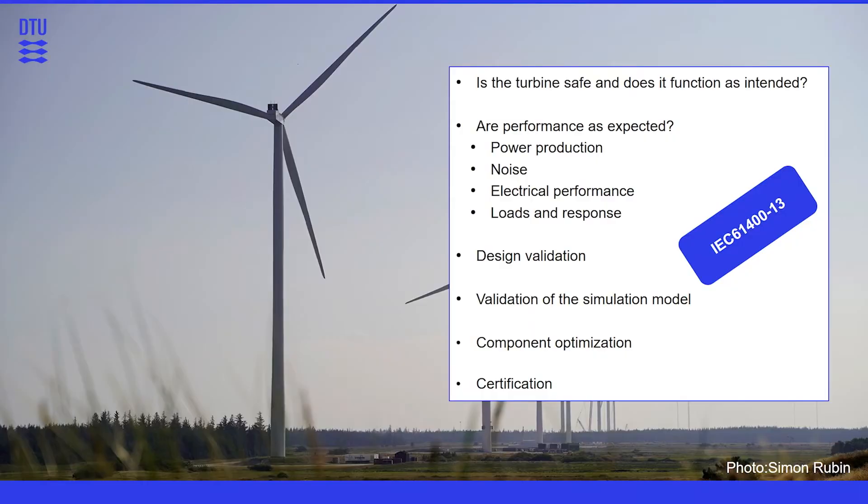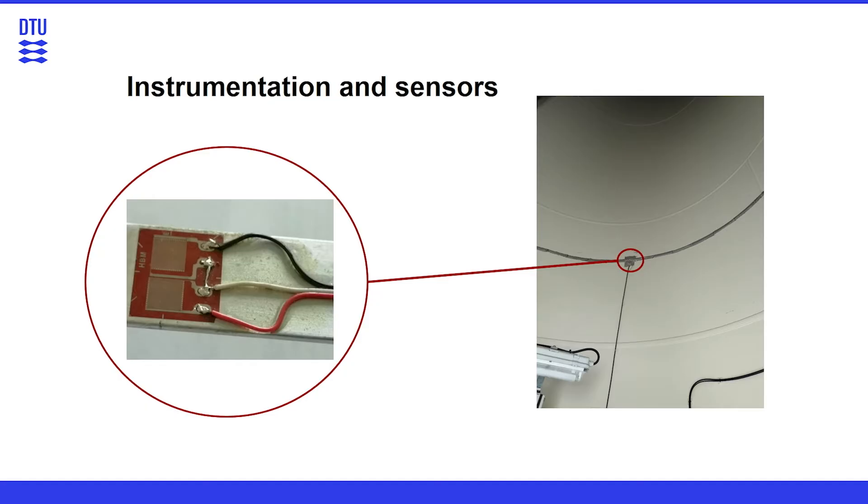And the international standard IEC 61400-13 is a very important standard for the load measurements. The way loads are measured on a turbine are various. There are many different sensors. A typical sensor for measuring loads is a strain gauge. We see one here in a close-up picture, and here we see it installed inside a tower of a turbine.